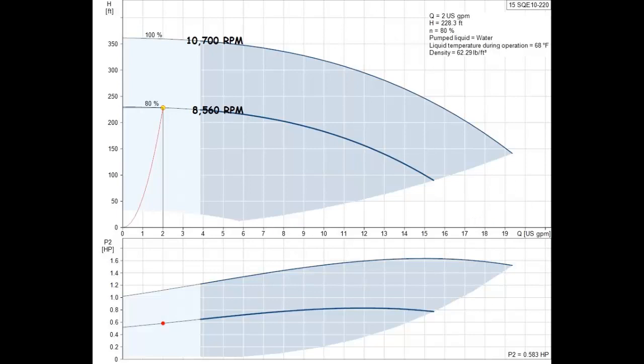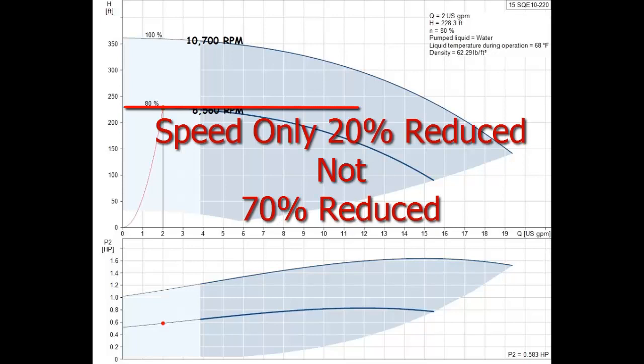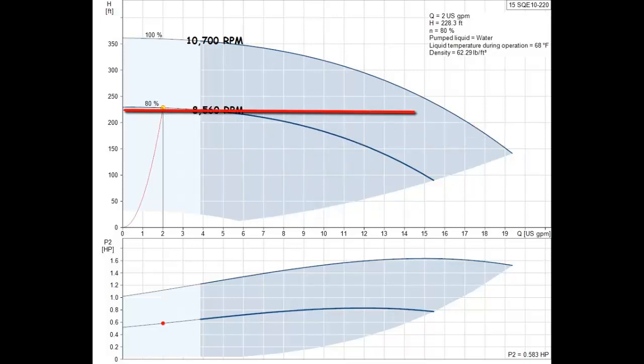The most this pump can be slowed down and still produce the 220 feet of head needed is only 20%, not 70% as many falsely believe. Anything lower than 80% of full speed will not lift water out of the well or produce pressure to the faucets. And since 80% of full speed is the slowest speed possible, reducing energy consumption by the cube of the speed doesn't add up to much.